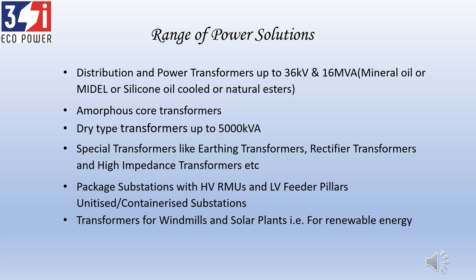We can manufacture transformers up to 16 MVA, 66 kV class. We are conversant with MIDEL oil, esters, and silicon oil, and we make amorphous core transformers which are very energy efficient. We import coils and assemble them at our factory. We supply many shopping malls in and around Chennai with added switchgear as package substations. We also make special transformers like earthing transformers, rectifiers, high impedance transformers, spot network transformers for lineways, and open delta transformers.